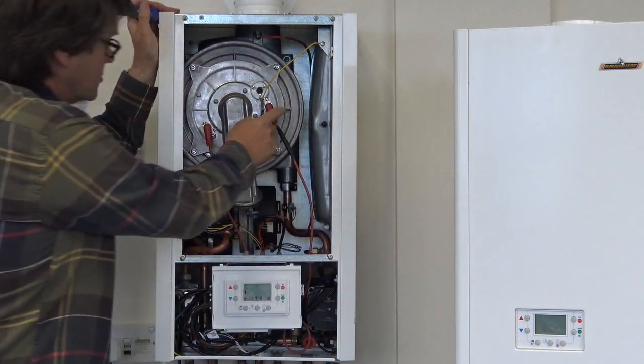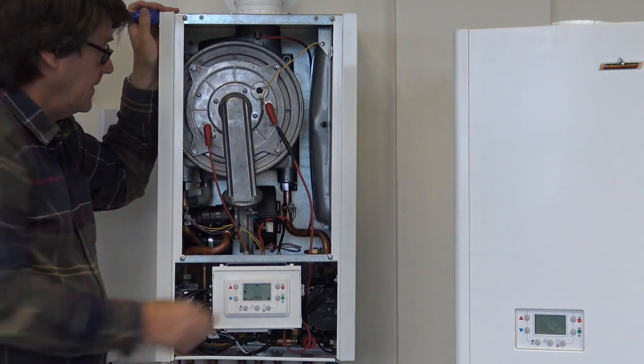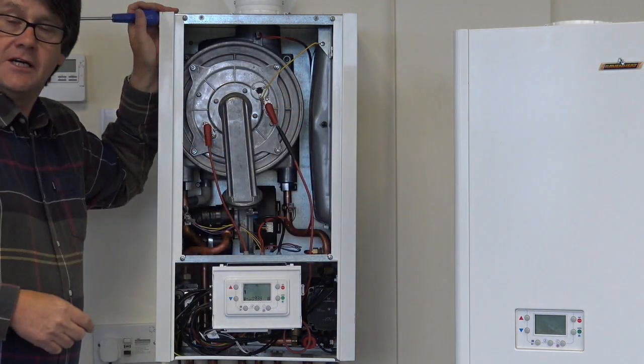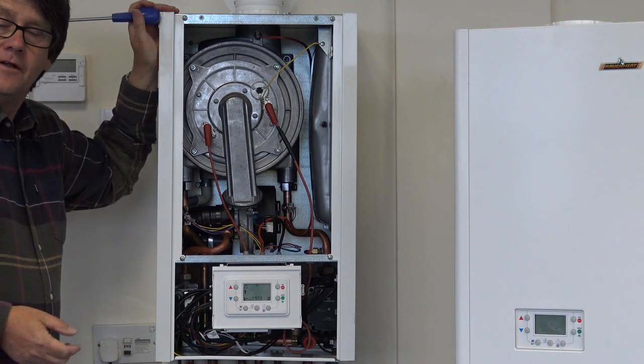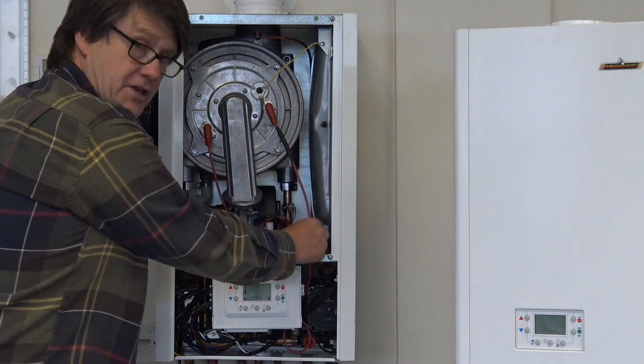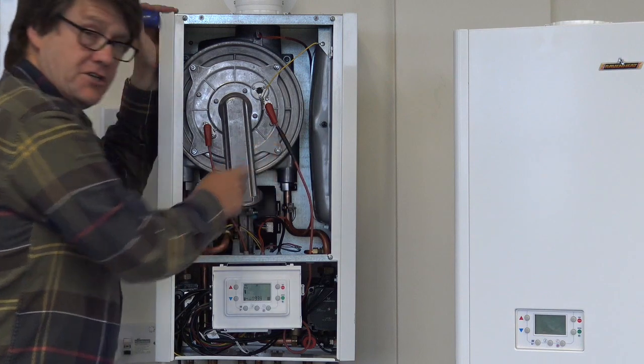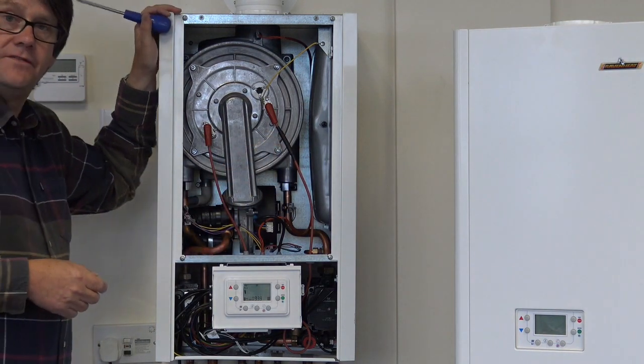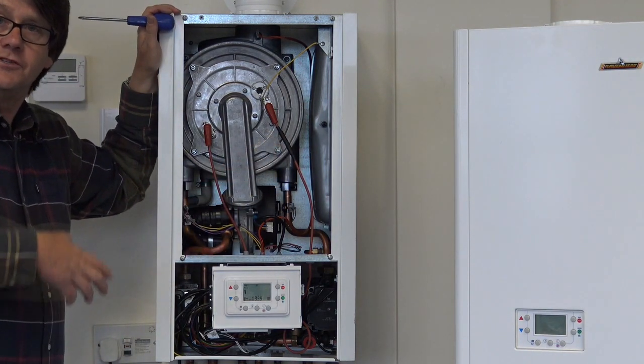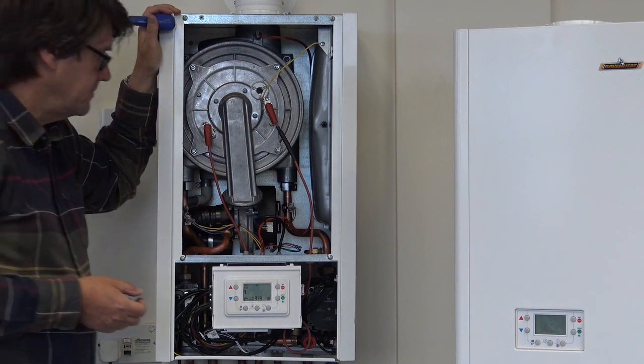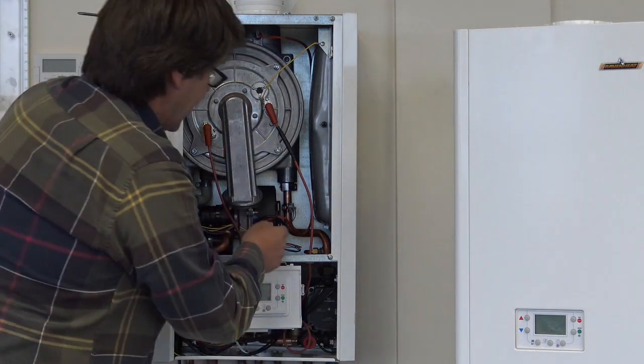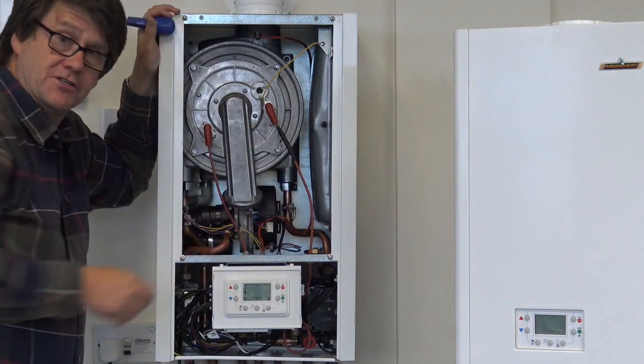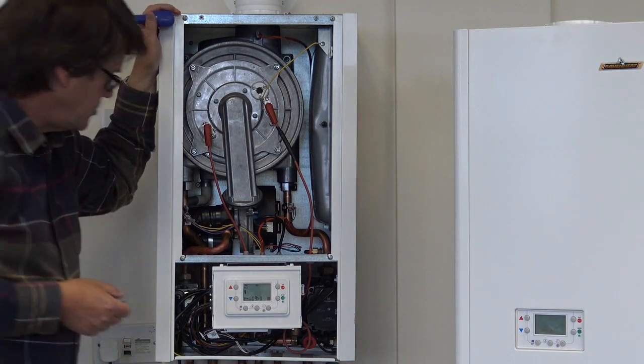Drop down, we've got spark, we've got rectification. Just look at the quality of these leads. They're not braided cloth. Thick rubber. A massive resistor on that spark. That stops any interference with TVs and radios, which the customer can complain of. Okay? Come down. Clip-on thermistors on the flow and return so you have no water issues.